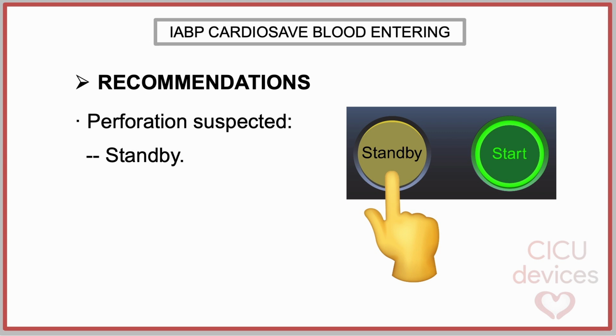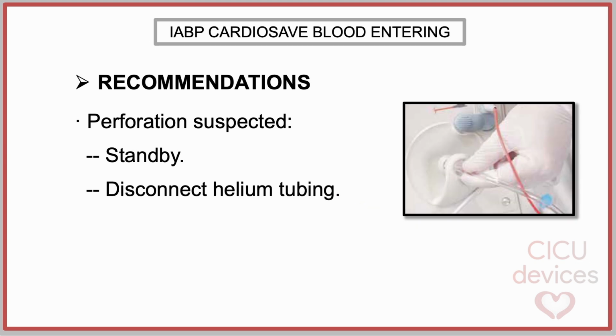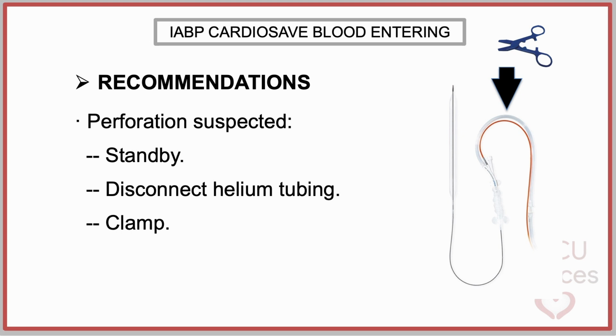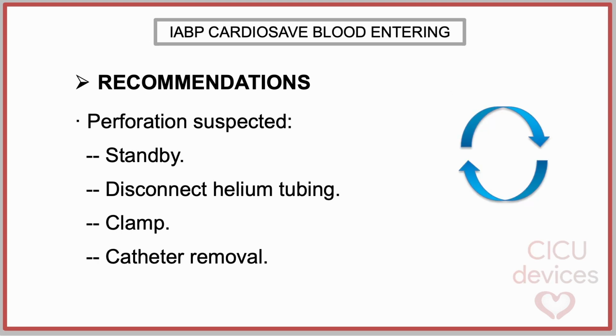If balloon perforation is suspected, clinicians must immediately place the IABP in standby mode by pressing the standby button on the console. Disconnect the helium extender tubing from the driving unit and clamp the helium tubing between the Y fitting and the male connector. Prepare for possible removal of the IAB catheter and assess the patient's need for ongoing circulatory support, considering insertion of a new IABP or escalation to an alternative mechanical circulatory support device, such as Impella or ECMO, if clinically warranted.